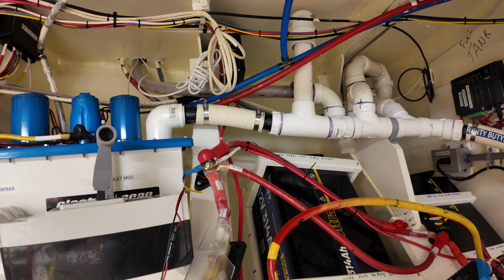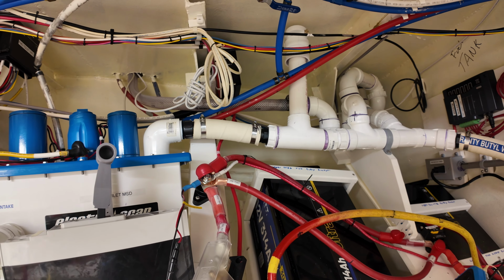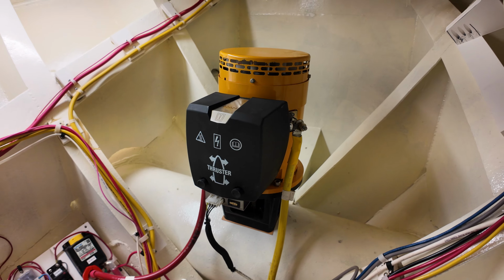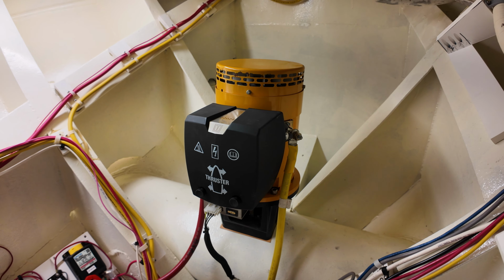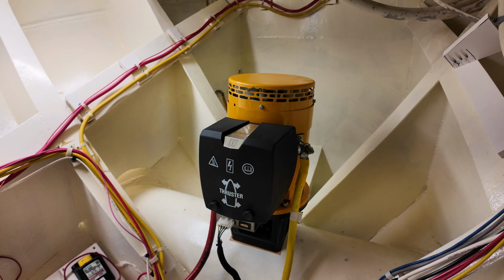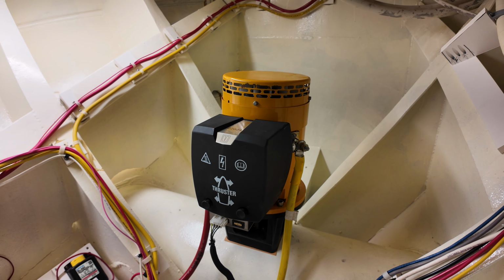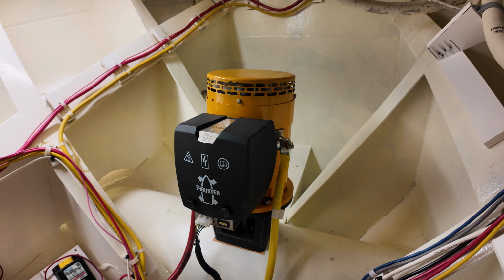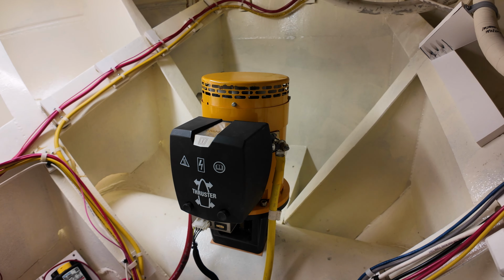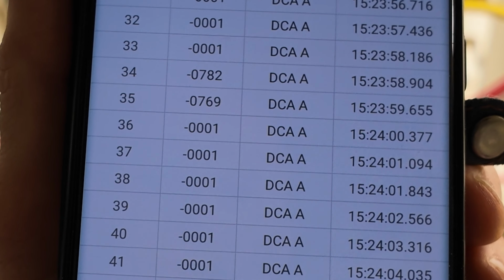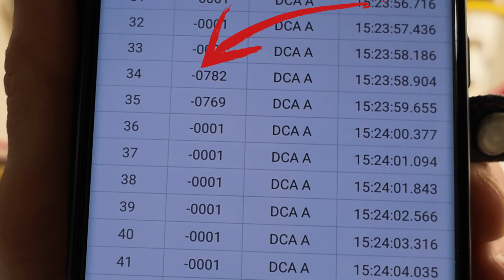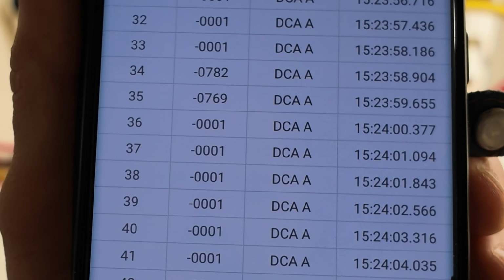But we still have issues with the battery's BMS dropping out. The bow thruster has a 500 amp fuse, so I thought it was close to 500 amps of current. That's not the case - we actually were able to get a good meter reading on it, and it was showing 782 amps, I believe.